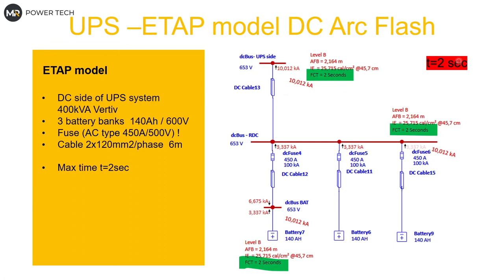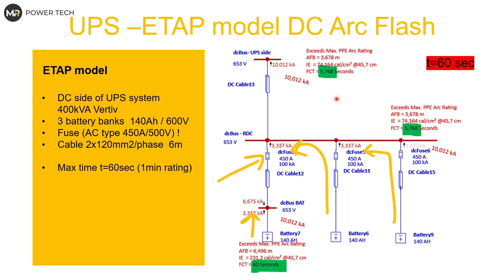Initially I set the calculation for the two-second rule from NFPA just to check results. We ended up with 25 cal/cm² everywhere at two seconds — clearly not correct, something had to be done with the protection. I then extended the limit to 60 seconds to see what would actually happen. On the main bus, it came to 74 cal/cm² because it took almost six seconds to trip — a very long time. And on each battery, making a fault on the battery itself showed 230 cal/cm² at 60 seconds — a huge amount, taking nearly a full minute.